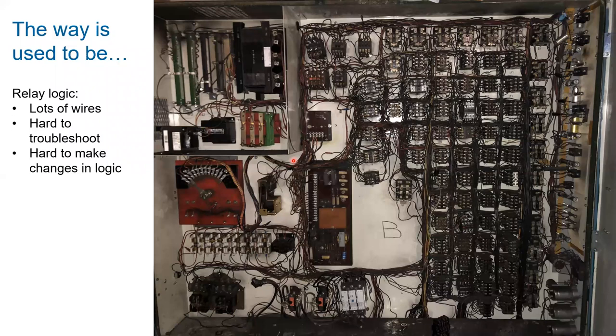The other reason why the PLC is important is because this is what it used to look like. So the previous diagram was very straightforward, right? It was just a simple kind of one little circuit, you know, relay. This is basically relays. All these little black bases here are relays. So this panel is a nightmare. Begin to try to even figure out, try to troubleshoot something that's in this panel, right? You've got a rat's nest of wires, nothing's labeled. You've got 30 different relays sitting in this panel at least. If you don't have a good set of drawings, can you even begin to troubleshoot this stuff? So it'd be very, very difficult to troubleshoot.